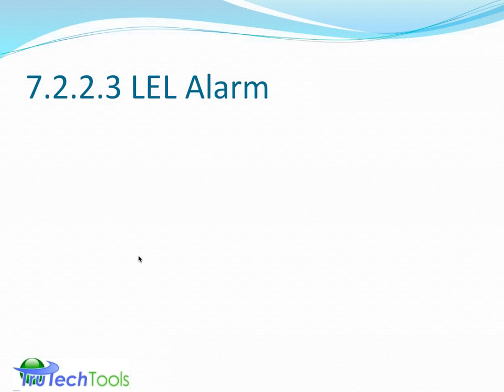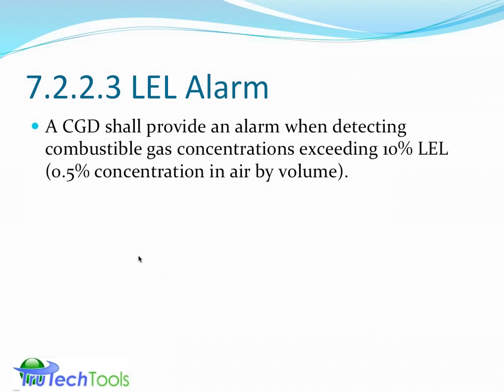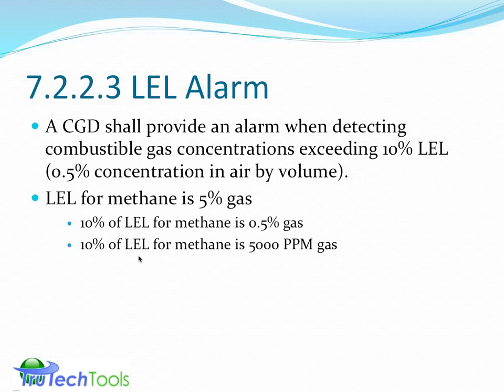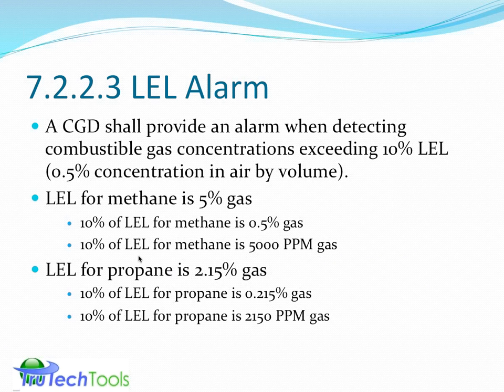The standard also, at this point of review, also requires an LEL alarm. We'll get into what LEL means a little bit more completely, but it stands for lower explosive limit. So what the standard is looking for right now in its present state, and again, things could be in flux, things might change, but the combustible gas detector should provide an alarm when detecting concentrations exceeding 10% of the lower explosive limit, which is 0.5% concentration in air by volume. That would be like 5,000 parts per million by volume for methane gas, which is the most typical gas. That, however, is a different amount of gas for propane.